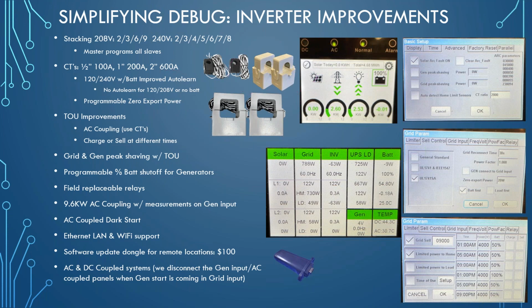We use those for a couple different modes. One, you can just get some nice data on the power usage of the building. But most commonly, we use it for what's called limited to home mode, or in other words, meter zero mode, so that if you don't have a net metering agreement yet, you can still produce power and just make sure that your meter tries to get as close to a standstill as possible. And as close as possible is actually programmable. We have a net zero power target that is programmable in the settings, which is pretty handy. If you want to give yourself a little bit more of a buffer or less of a buffer, you absolutely can.